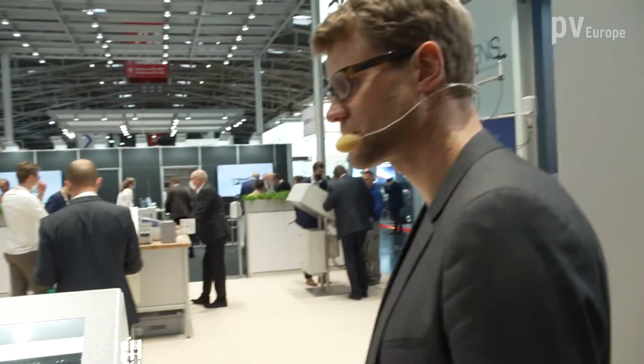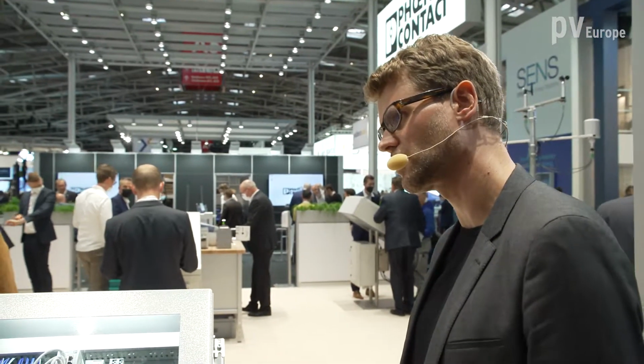Let's talk about the communication. How does this work with the grid operator and direct marketer? We have 2 different interfaces. One to the direct marketer, that's easy, handled by the 101 or 104 protocol. In addition, we have to have communication to the grid operator, and that's sometimes tricky, especially in Germany, because we have around 900 different grid operators, meaning 900 different expectations and requirements. That is done by installation, programming and commissioning through our so-called solution partners, system integrators who do this customization and installation on site.